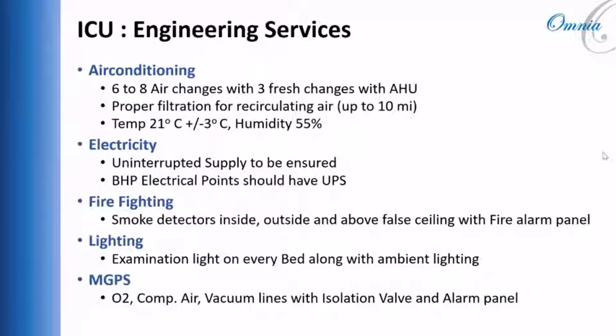For the medical gas piping system, O2, compressed air, and vacuum lines with isolation valve and alarm panel should be provided. The number of outlets for O2, compressed air, vacuum lines, and electrical points will depend on the type of ICU being planned.